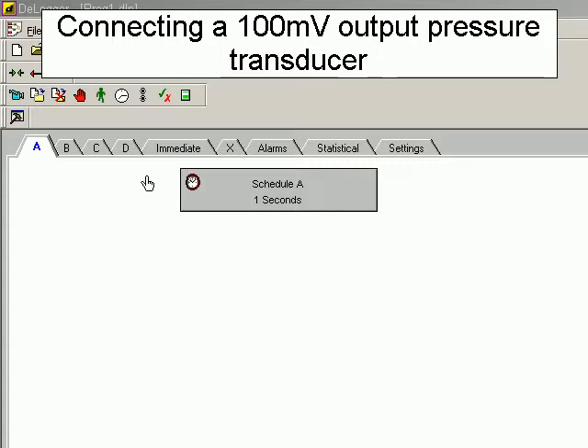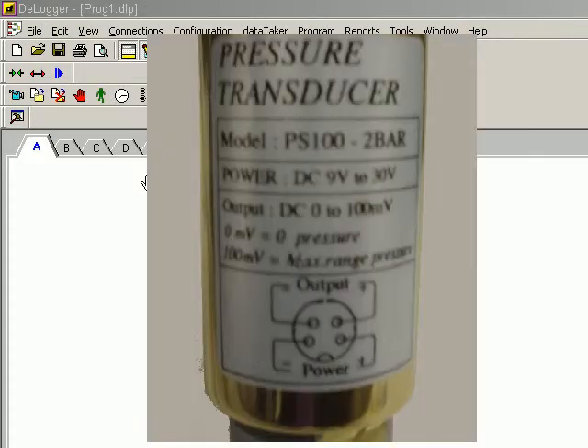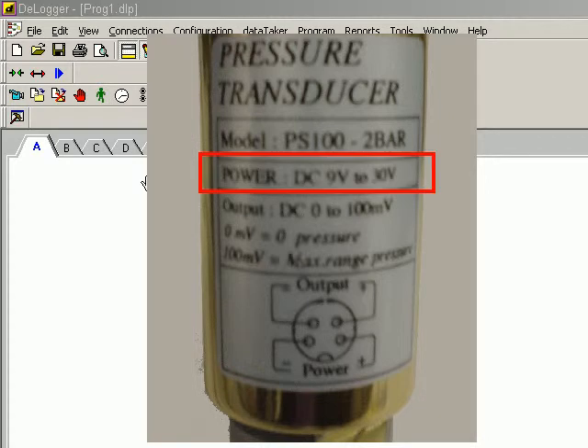This sensor example demonstrates connecting a pressure transducer with a 100 millivolt full-scale output. If we look at the wiring diagram on the side of the transducer, we see that we need a 9 to 30 volt supply.